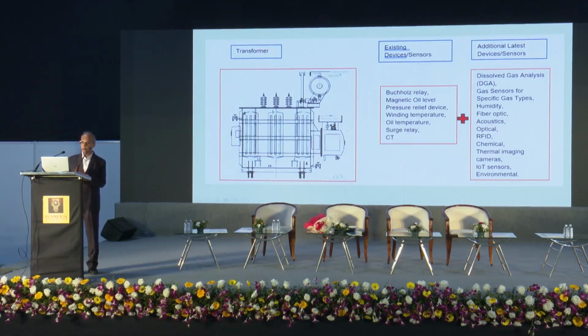Now, up till now, when we see the transformers, for the protection of the transformer, what did we use to give? It was the Buchholz relay, maximum. There could be the MOL, magnetic oil level. There could be the temperatures, oil temperature, winding temperatures. There could be the surge relay, when you are having the OLTC, and the CT. I suppose other than this, we do not use anything else, right? We have got this much only for the protection of the transformer.